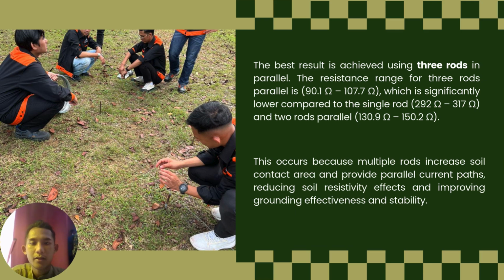So the next slide: the best result is achieved using three rods in parallel, which is the previous slide that we saw. The three rods that we use are the most effective and gave the lowest ohm result. So they must be in parallel positions to make sure we get the lowest ohms. Our group has achieved between 90.1 ohm until 107.7 ohms, which is significantly lower compared to the single rod, which is 292 ohms until 317 ohms, and the two rods in parallel, which is 130.9 ohm until 150.2 ohms.